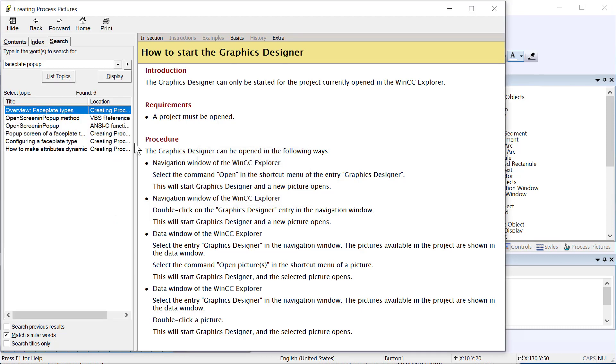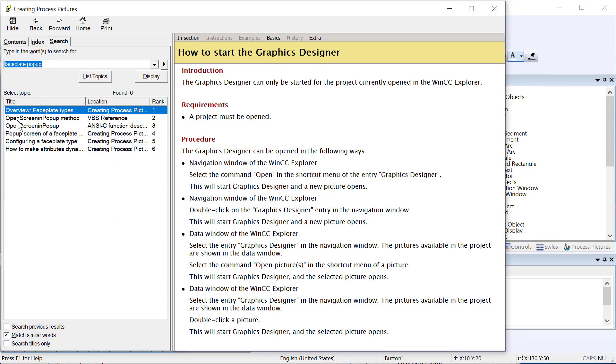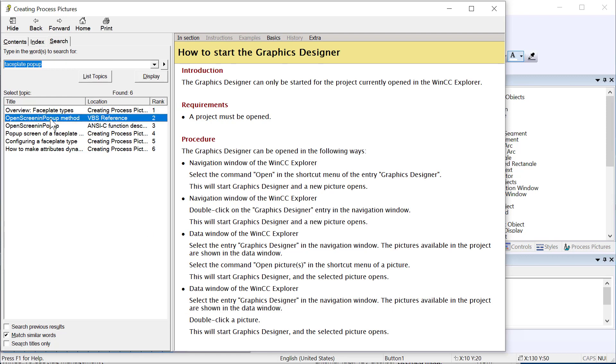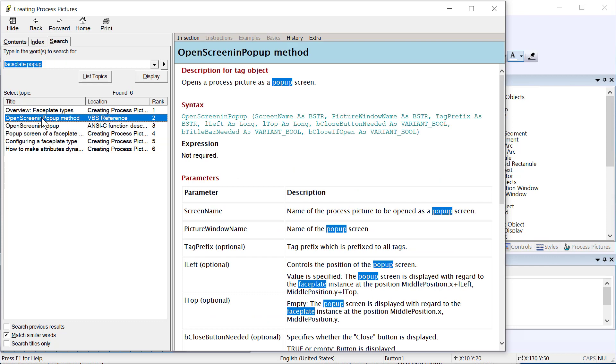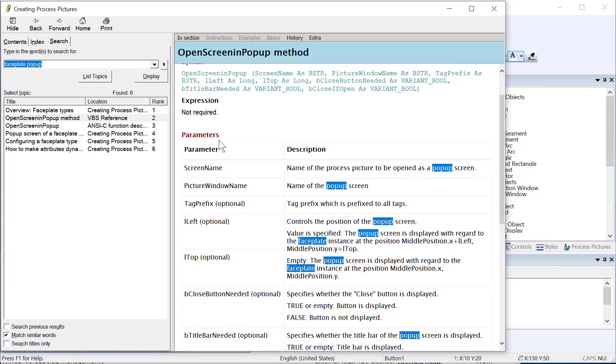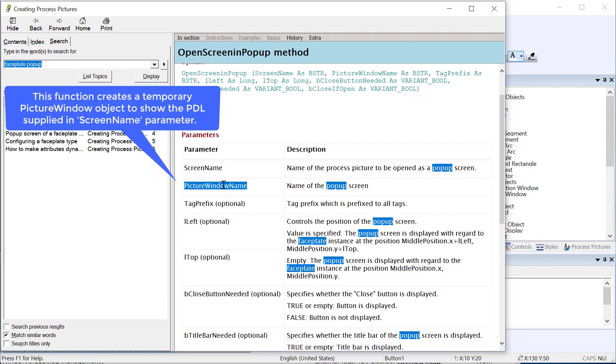If you go to search and just type in faceplate pop-up, we have a couple of topics. You can see we've got the OpenScreenInPopup method for VBS. We have one for ANSI-C. These are also used in faceplates to create detailed pop-ups for faceplates. What I'm going to do is just open up the VBS reference. We've got our syntax here and we've got some required arguments and then we've got some that are optional. If you look at the parameters, these are listed in order. The screen name is going to be the name of the picture you want to pop up.